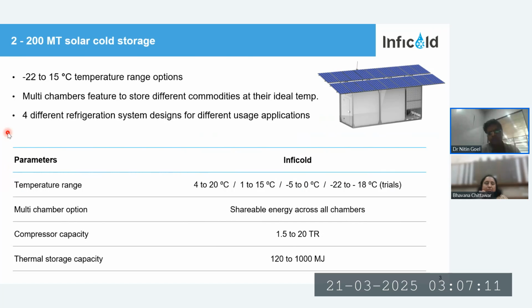One feature of these cold storages is their temperature range. They can go from 4 to 20 degrees, primarily meant for vegetables. For fruits, it can go from 1 to 15. Then -5 is for fish applications, and lower for frozen applications. The good part about solar cold storage is that they have multiple chambers.